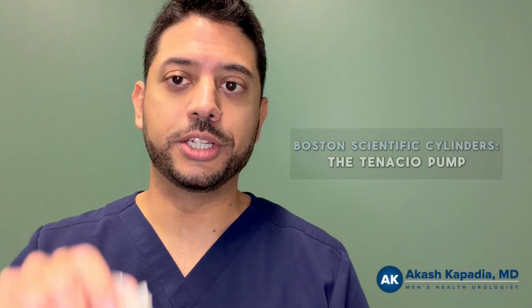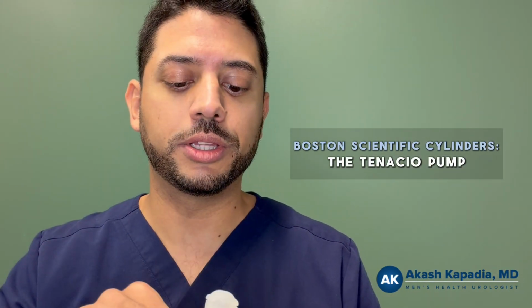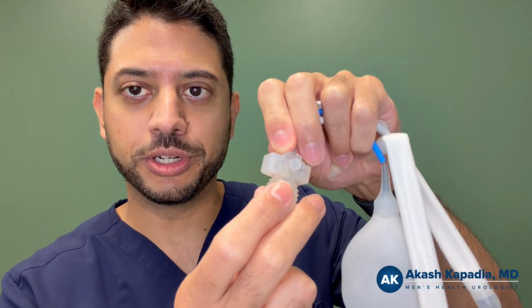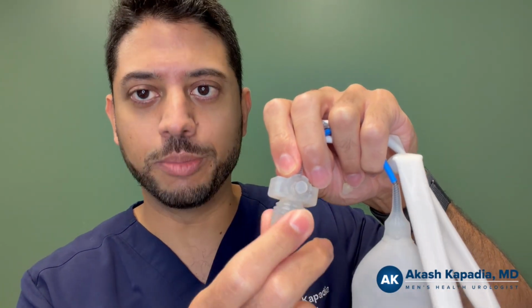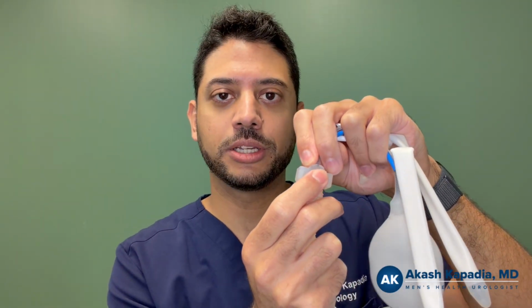Recently, Boston Scientific came out with what's called the Tenacio pump, just within the last year or year and a half. There were design changes mainly aimed at allowing better inflation of the device, which I think this pump may lag a little in comparison to the Coloplast pump. So the whole purpose of this device was to provide better inflation.